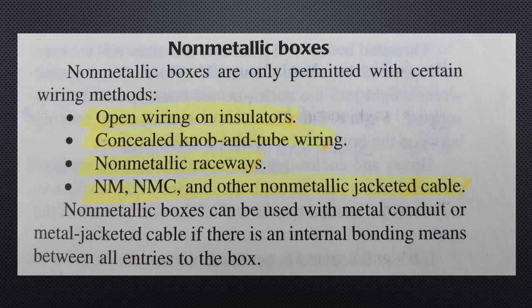Non-metallic boxes: non-metallic boxes are only permitted with certain wiring methods: open wiring on insulators, concealed knob and tube wiring, non-metallic raceway, and NM, NMC, and other non-metallic jacketed cable. Non-metallic boxes can be used with metal conduit or metal jacketed cable if there is an internal bonding means between all entries to the box.